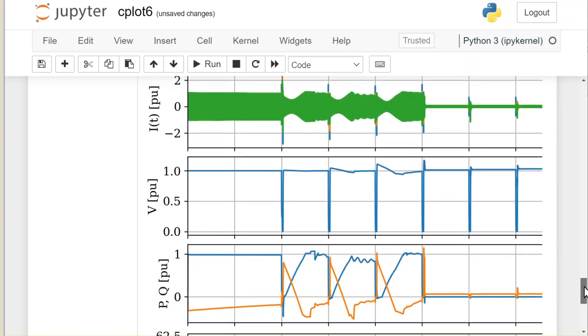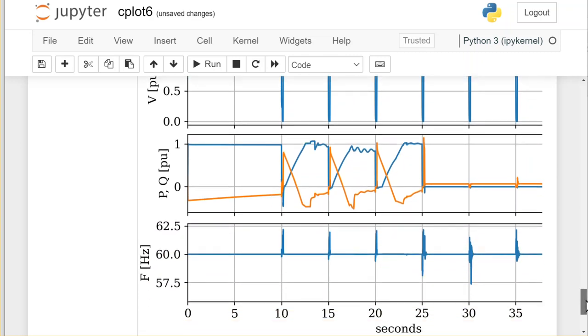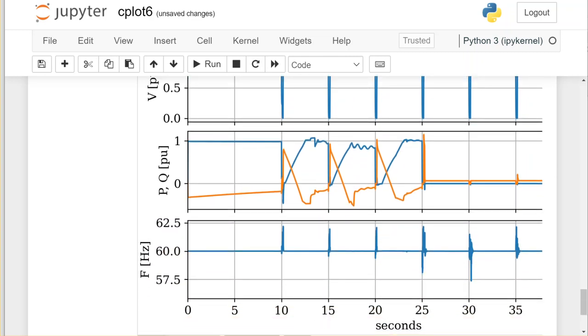The RMS voltage is estimated as, so you can see the successive faults at 5-second intervals, and each time the IBR comes back into service, it sees a higher source inductance. So it recovers from 3 of those events. So here at 10 seconds and at 15 seconds and at 20 seconds it comes back, but the fault at 25 seconds, when it comes back, the short circuit ratio is too low, so the power output is 0.